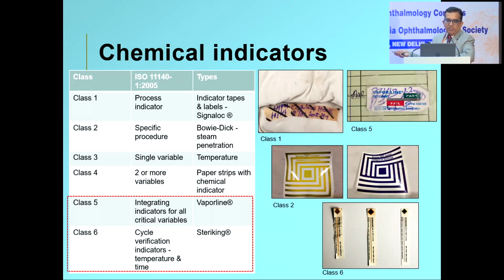The second is you need to have the Bowie-Dick. This is a Bowie-Dick that you get, and after sterilization it changes color. If it doesn't change color, that means the steam penetration within that load is inadequate. And then you need to have either a class 5 or class 6, because that assesses and validates the cycle time of your sterilizer.